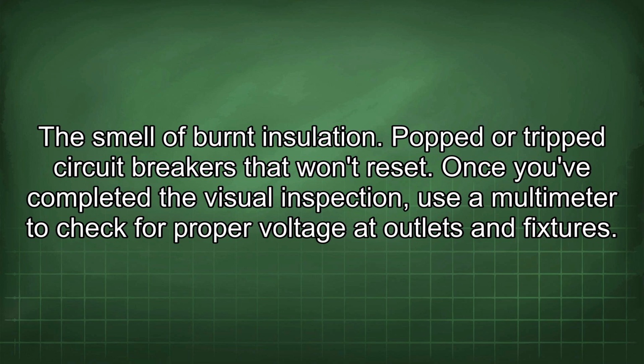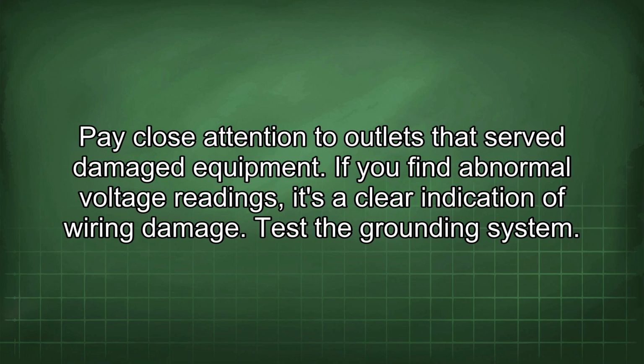Once you've completed the visual inspection, use a multimeter to check for proper voltage at outlets and fixtures. Pay close attention to outlets that serve damaged equipment. If you find abnormal voltage readings, it's a clear indication of wiring damage.